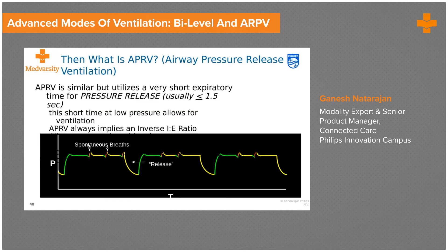Now let's move to another variant of BiPAP — this is called Airway Pressure Release Ventilation, or APRV. By nature it is extremely similar to BiPAP: you are ventilating on two pressures, a PEEP and an inspiratory pressure, and you have an active exhalation valve allowing unloading if the patient wants to breathe in the inspiratory phase. However, the key difference of APRV versus conventional BiPAP is that the I:E ratio is actually inversed — you have a far longer inspiratory cycle and a short, explosive expiratory cycle.